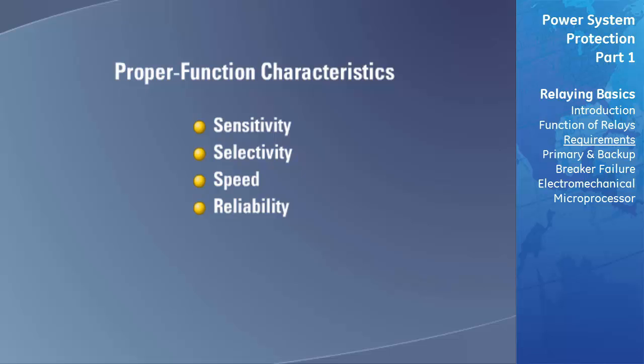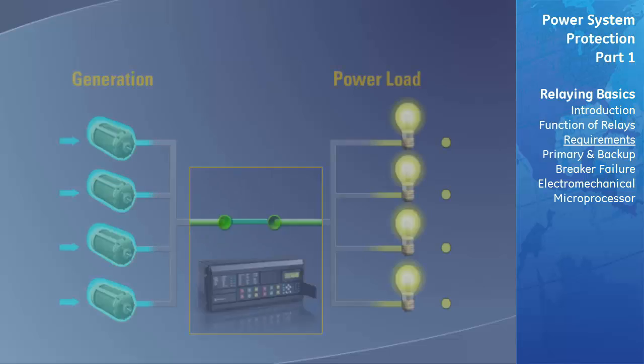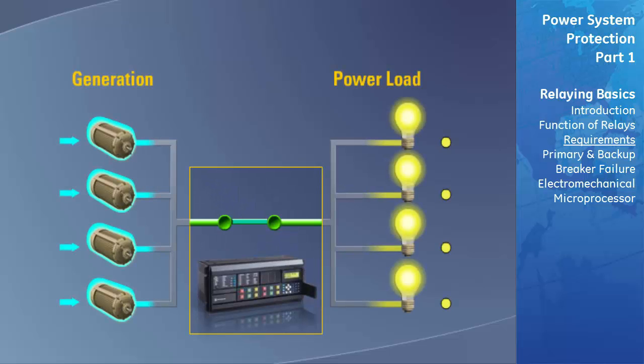The relay must be sensitive enough to operate under the minimum conditions expected. In any power system at various times of the day and during various seasons of the year, the load varies over a wide range. To meet these changing requirements, various combinations of generating sources are switched in and out of the system to provide efficient operation. The relay must be sensitive enough to detect a fault on the system when the minimum amount of power is being generated on the system.